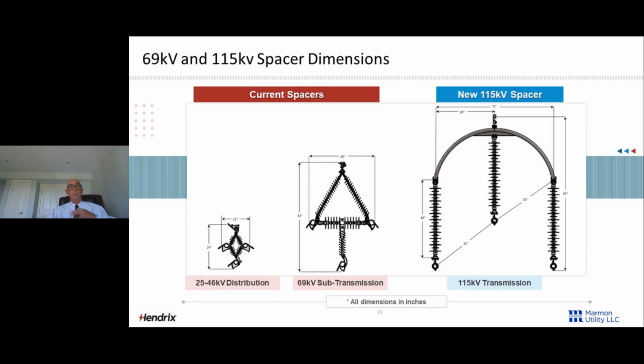So here's the spacer. I didn't even put in the 15 kV spacer. It's essentially the same size as the 25 kV spacer. We didn't need to put it. You can see when I get to the 69 kV spacer, instead of 24 inches high, it's 63 inches high. Instead of 15 inches wide, it's 40 inches wide. When we go to the new 115 kV spacer, yes, it is quite a bit larger, 93 high and essentially 71 wide. So different ball game there at 115 kV.